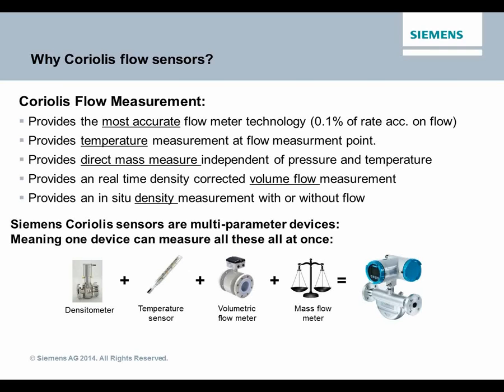It's not dependent on a pressure reading or a temperature reading for correction. Even though the temperature sensor that I just mentioned allows for the meter to confirm that the tube is vibrating appropriately at that temperature, the mass is the mass, and a pound does not change just because it gets hotter.